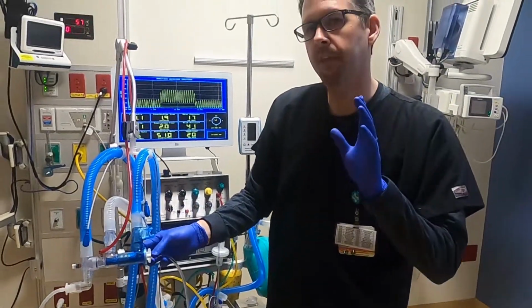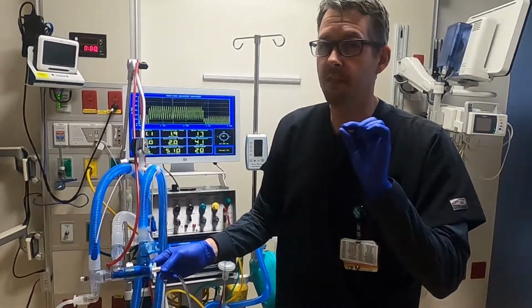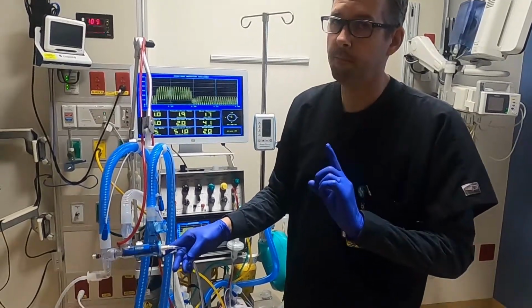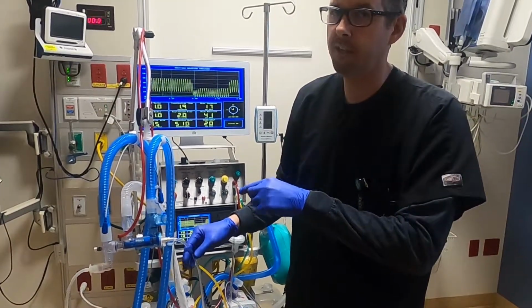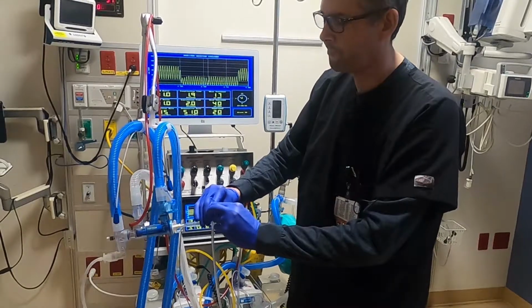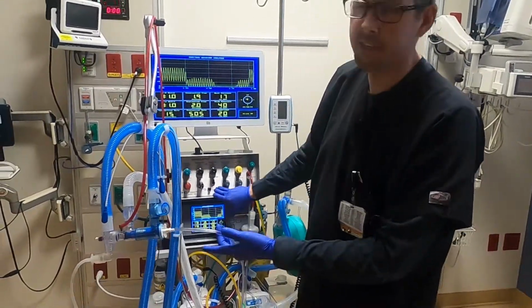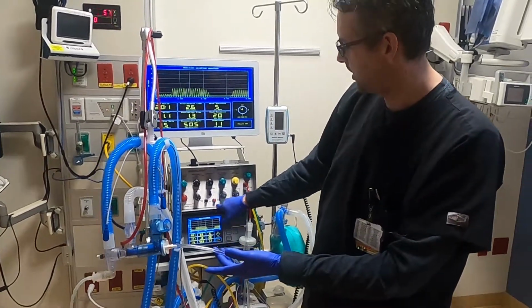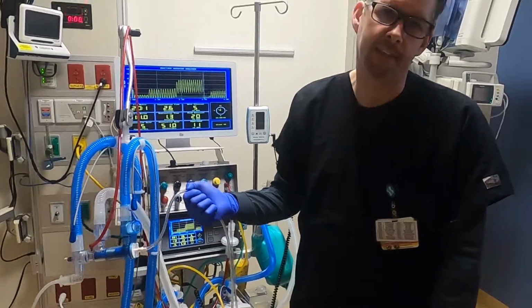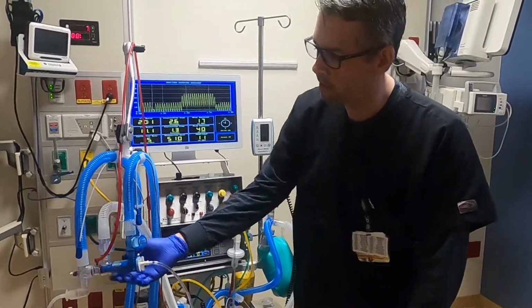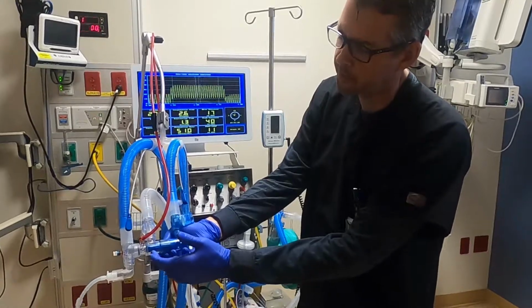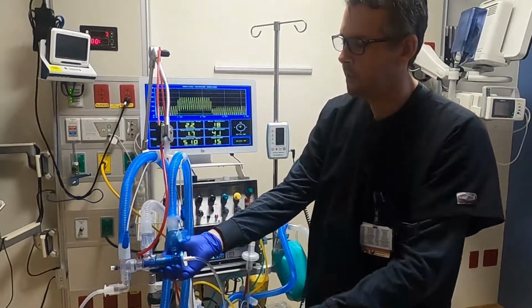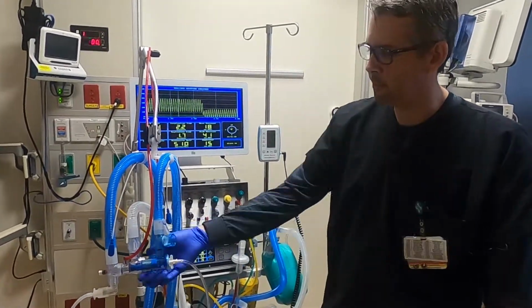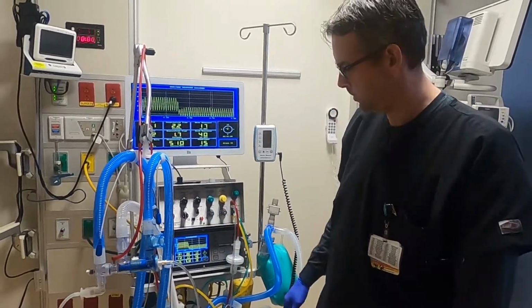I just want to show you what the alarm sounds like if the working pressure line gets plugged and shuts down the phasitron. That's what it sounds like. And then you just reset here. That's usually because it's kinked, or there's something going on with the phasitron. There's something that's built up in here and it's blocked. In that case, you would have to just change the phasitron out.